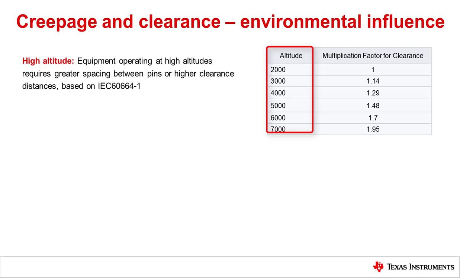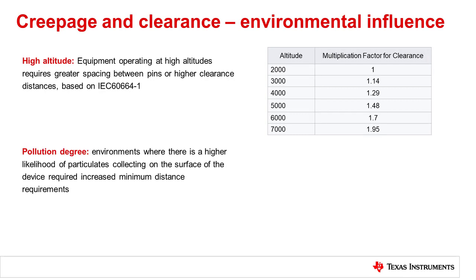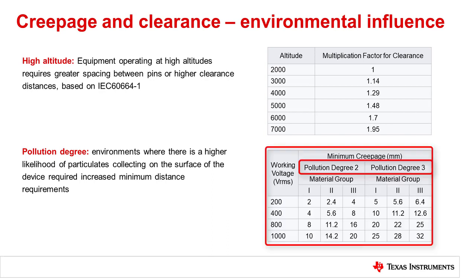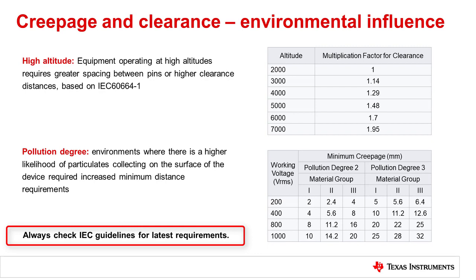Equipment operating at high altitudes requires greater spacing between pins or higher clearance distances based on IEC 60664-1, which provides multiplication factors by which clearance must be increased at higher altitudes in order to protect from altitude-induced arcing. Similarly, in operating environments where there is a higher likelihood of particulates collecting on the surface of the device and thereby creating conductive pathways, the consideration of pollution degree will also influence minimum distance requirements. Both altitude and pollution levels are rated for the end equipment operating environment from the end equipment standards, so it's wise to always check IEC guidelines for the latest standard.